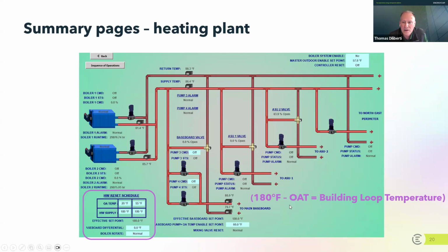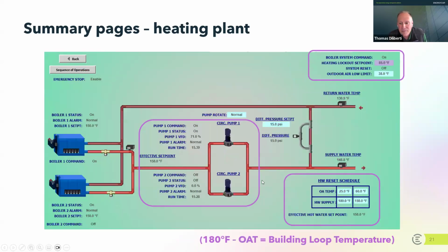You want to follow this rule that I introduced earlier. It's 180 degrees minus the outside air temperature would give you the loop temperature. And this is saying that it's always going to be 180 degrees. So this is a huge opportunity for savings. So if any of you encounter this, I would take a look at that. And this is what you're going to want to see. This next slide is an example of one that's set better. What this is saying is when the outside air temperature is 25, I should say, the hot water supply is 180. But when the outside temperature is 60, now this is programmed to become 150.